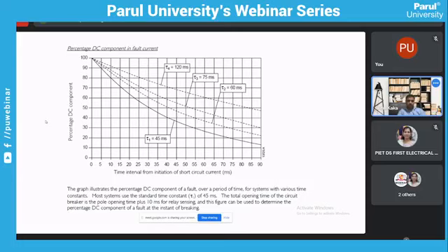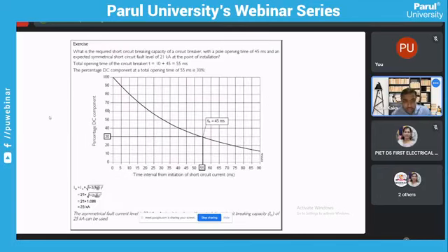So the opening time of the circuit breaker is the pole opening time plus 10 millisecond of the relay sensing. That is something described in the next figure. So what we can see here is what is required: the short circuit breaking capacity of the circuit breaker with a pole opening time of 45 milliseconds. This is just a rough example for a symmetrical short circuit of 21 kA at the point of installation.